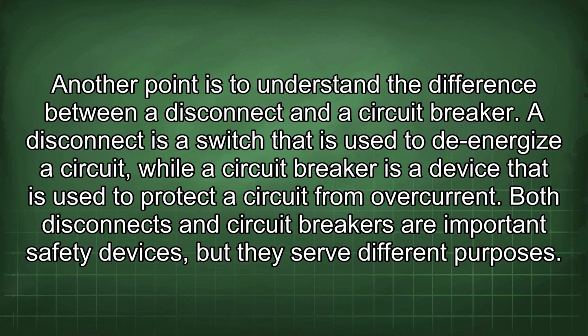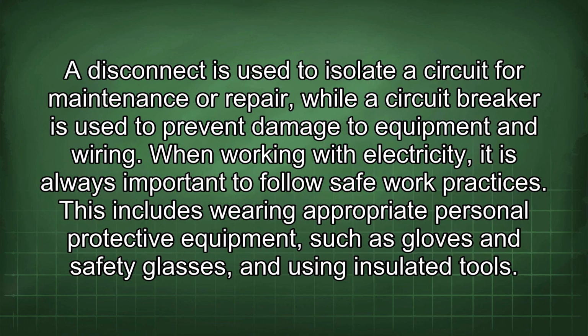Another point is to understand the difference between a disconnect and a circuit breaker. A disconnect is a switch that is used to de-energize a circuit, while a circuit breaker is a device that is used to protect a circuit from overcurrent. Both disconnects and circuit breakers are important safety devices, but they serve different purposes. A disconnect is used to isolate a circuit for maintenance or repair, while a circuit breaker is used to prevent damage to equipment and wiring.